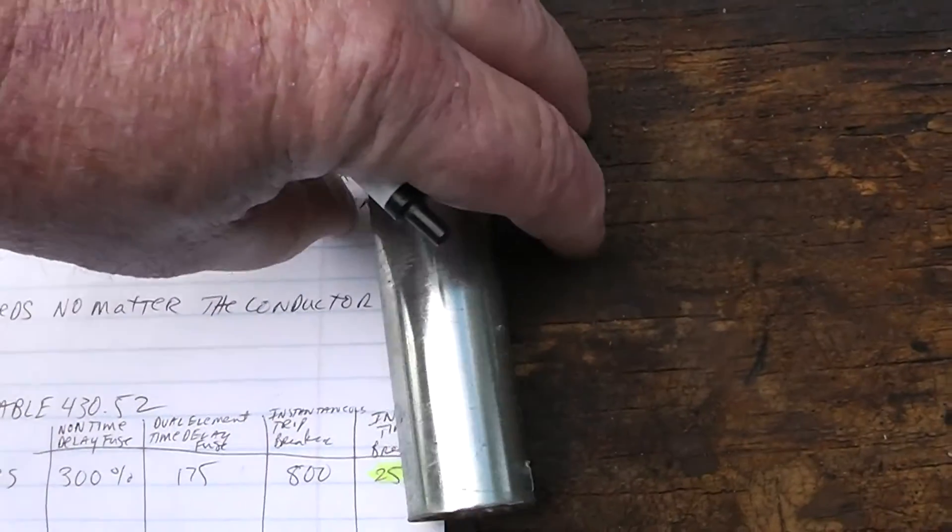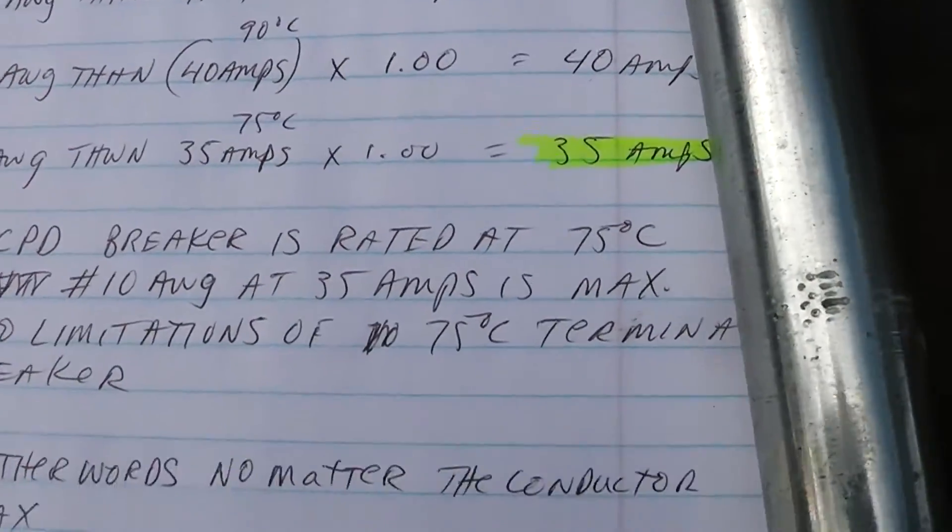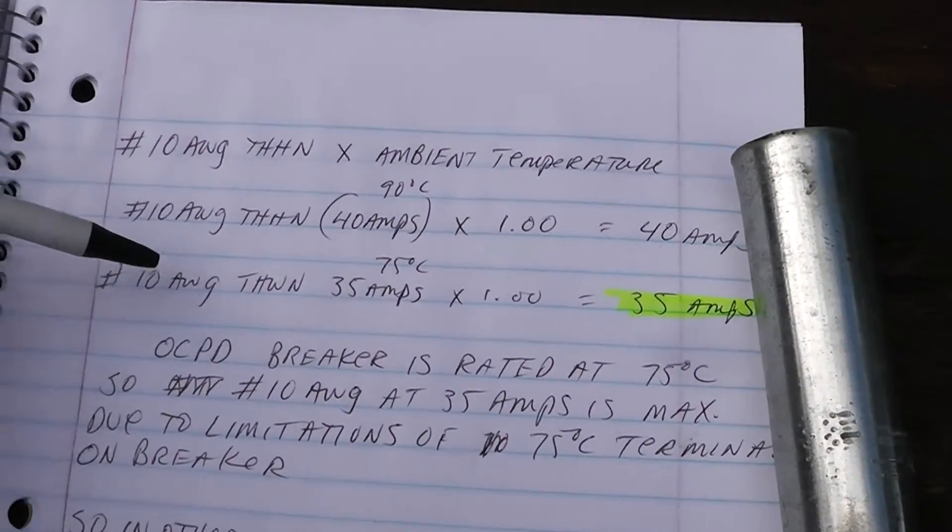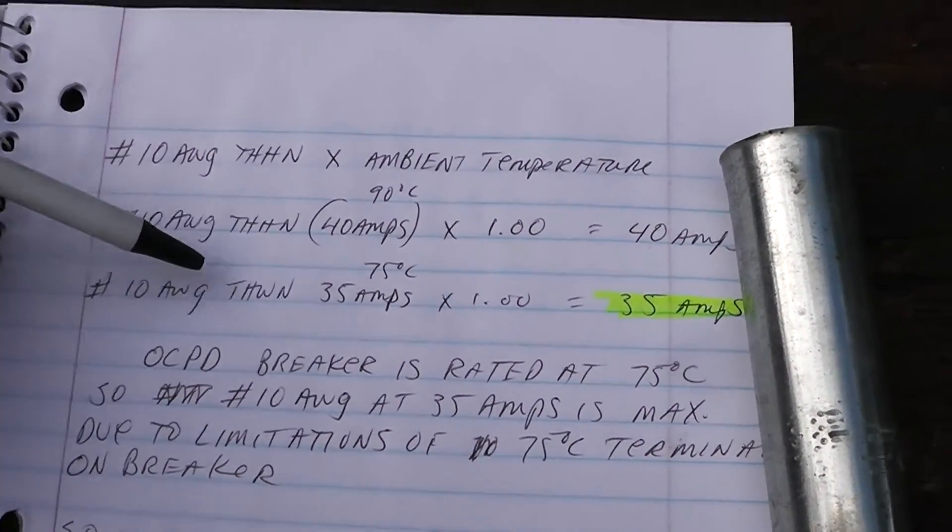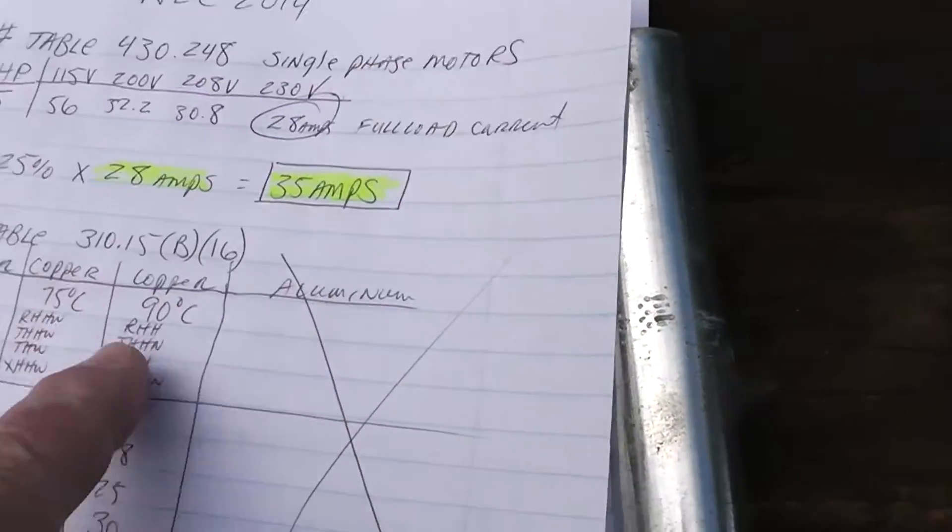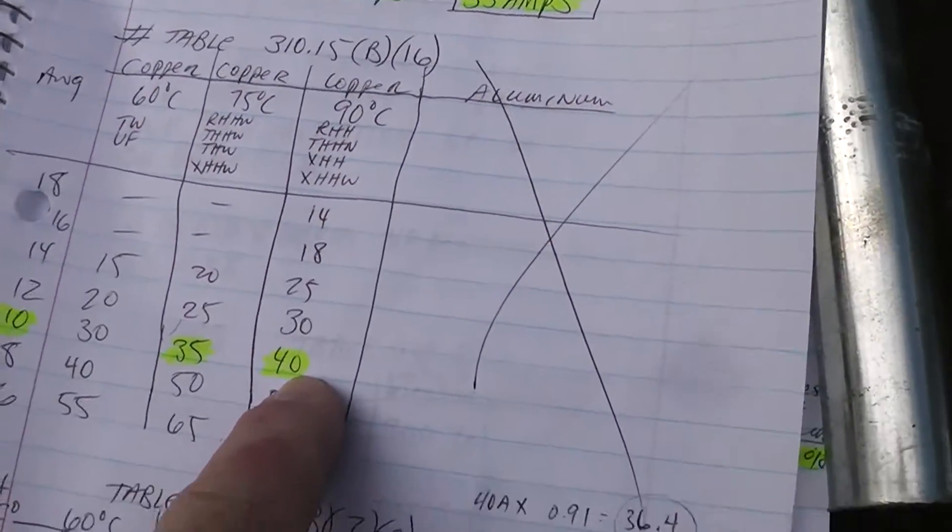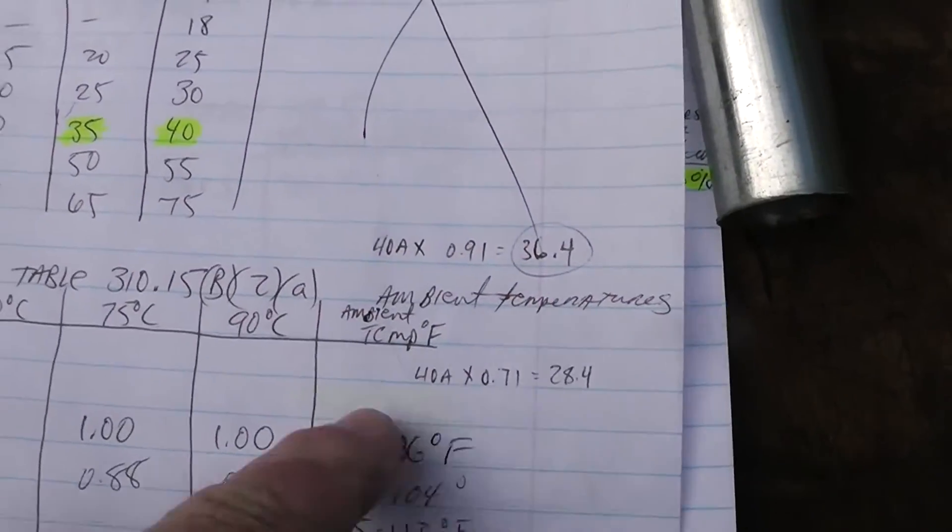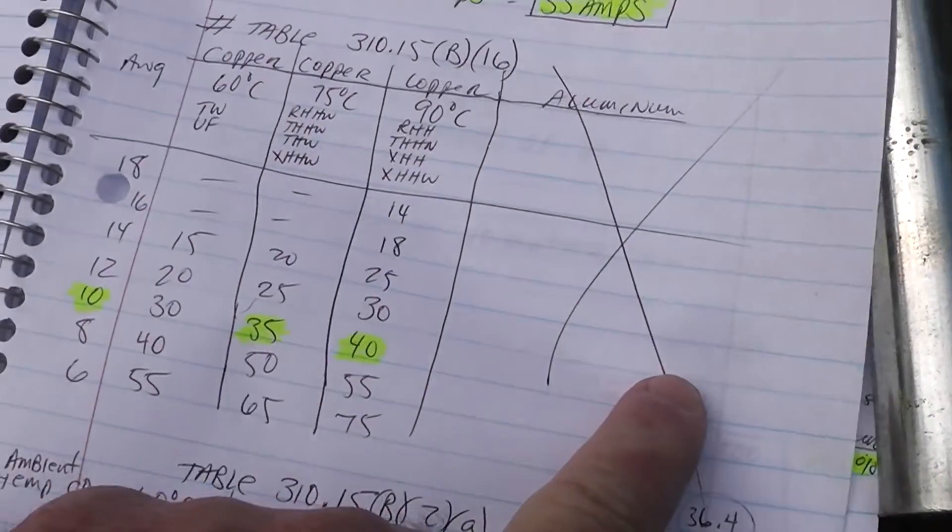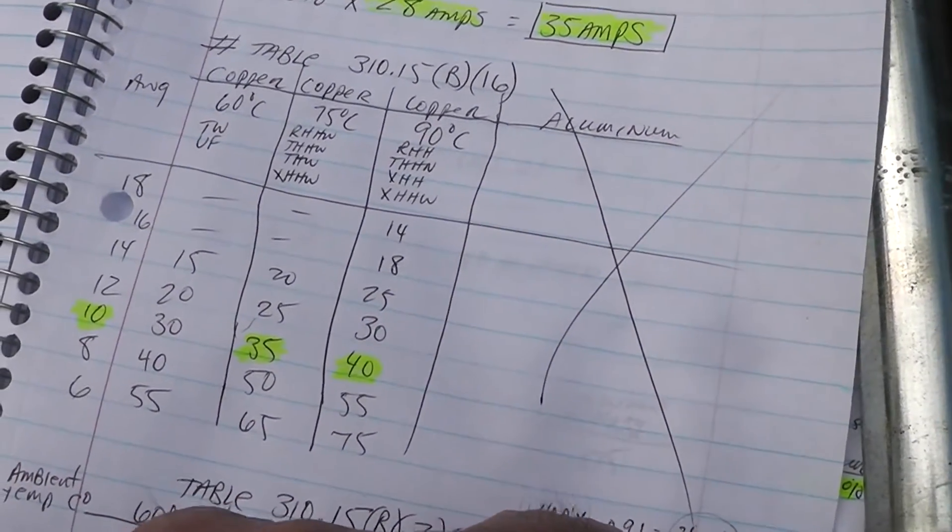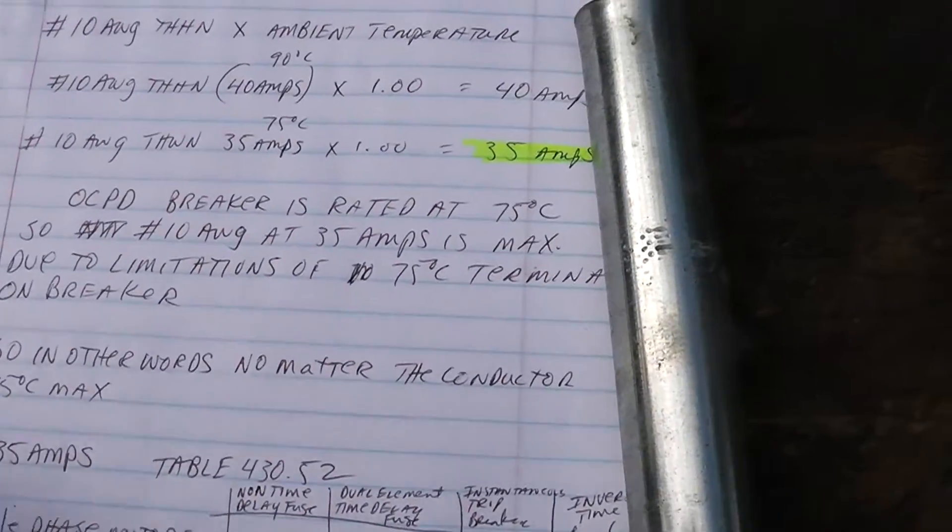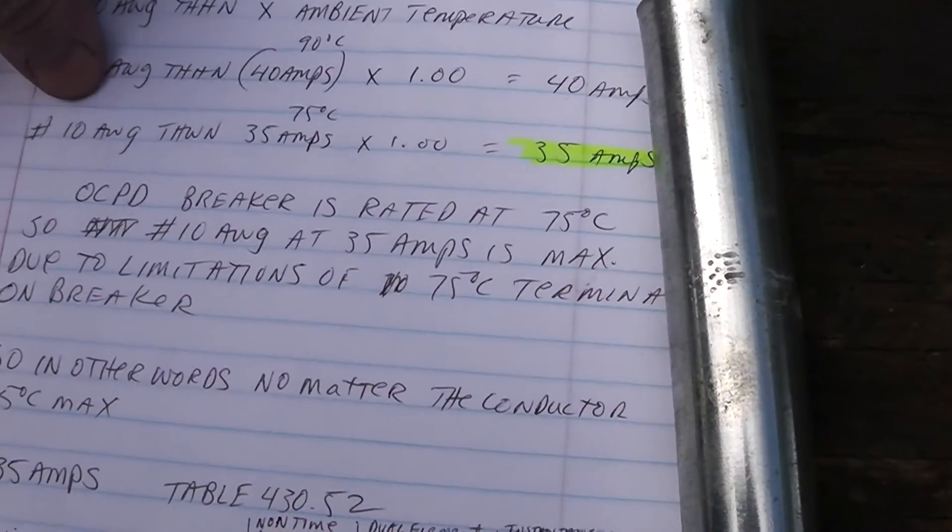Another thing is we are limited by the breaker. The breaker terminals are rated for 75 degrees Celsius. Even though we're using this wire and we can use it to calculate the ambient temperature variations, we can never go above 35 amps on it. So we are maxed out.